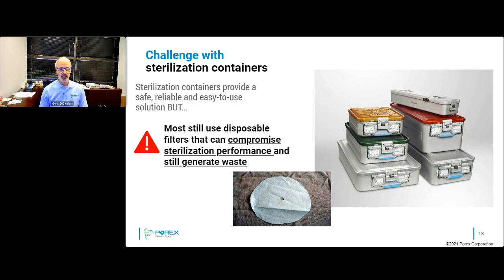Also, in the photo below, you can see how this one is wrinkled a bit. Certainly, it was done purposely, but that can happen with these filters. If the paper that they cut it out of has been folded and there's a wrinkle in it, that wrinkle, as you put it in the device, can be another break in the seal. And even if you do have a material you're using with a relatively high bacterial filtration efficiency in the 90s, breaking that seal with a fold or a crease reduces it dramatically. So again, if you want to go to a sustainable solution and look at containers that are reusable, then shouldn't you think about going all the way and using filters that are also reusable?